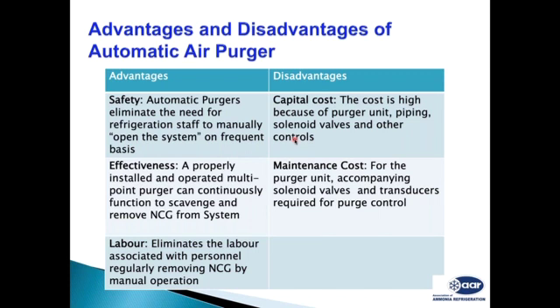As I talk about manual and automatic purging, what are the advantages of automatic purging? Automatic purging removes air online, continuously, without affecting the system performance. No need to shut down the system. No need to have an operator to operate it. And as it is an online system, it removes air immediately. There is no labor cost. There are no safety requirements. There is no manual intervention required in operating this purger.